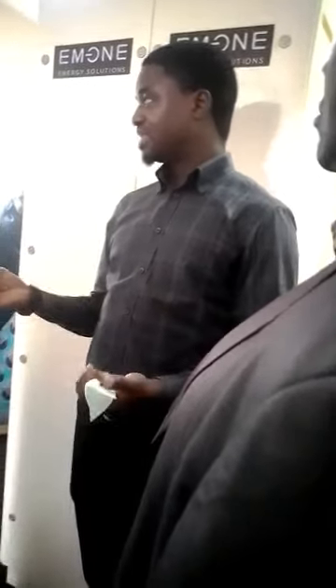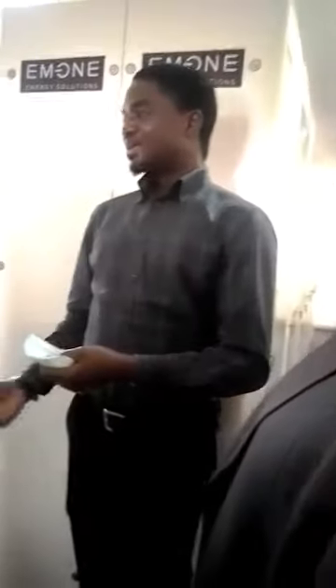So if the system needs to control the PV power instantaneously because there's a situation where PV power is high — meaning there's a lot of sun, the battery is full, and the load is low — what do you do with the power? The PV power is now in excess, there's nowhere for it to go, the battery is full and doesn't need more, and the load is low. Even though that's a simple explanation, it's actually a very serious situation. Basically, the controller will control the frequency of the battery, keeping it between 50 Hz and 50.5 Hz or 51 Hz.